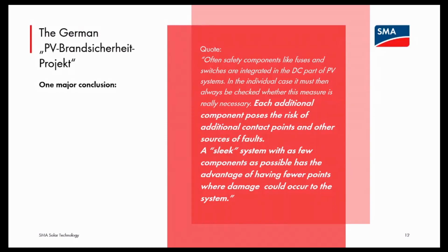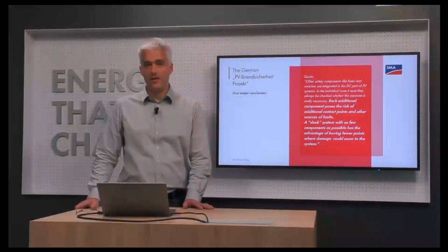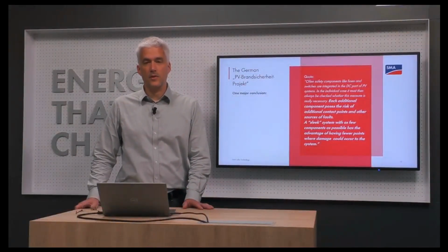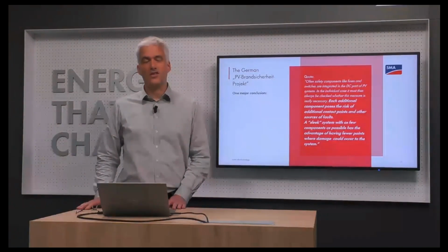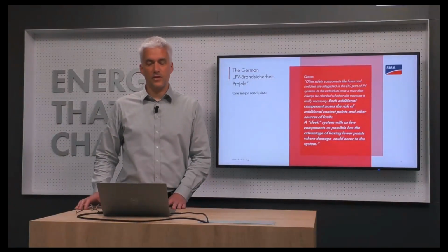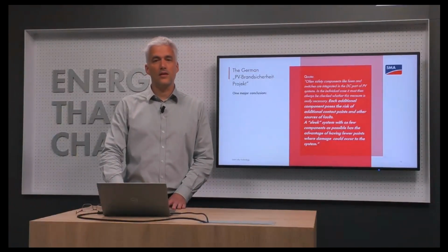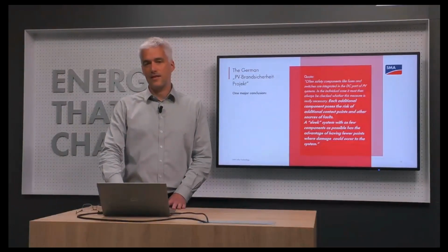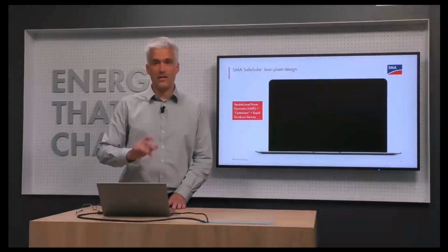A sleek system with as few components as possible has the advantage of having fewer points where damage could occur in the system. So more complexity means more potential points of failure, higher risk. So if you start adding components, for example, for rapid shutdown, you're actually increasing the risk rather than reducing it. That's a very important takeaway from this study, I think. And let's further dive into this and try to explain what that means and how this actually comes to be.